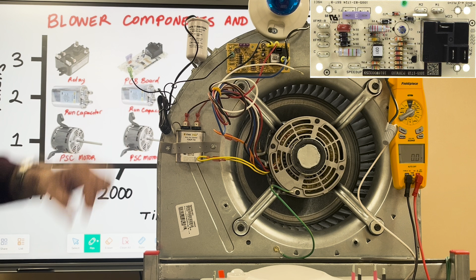We've just put this here so we can give it a fault and you can see what happens. All the wires that I have with connectors are all landed. At this point we can just take a bunch of alligator clips and start wiring this up. I'm doing it this way just for safety. When I get to the smart board I'll wire it up in a different order. Typically I always try to work with high voltage and then go down to low voltage, so we're kind of in the same order that we would normally go in.